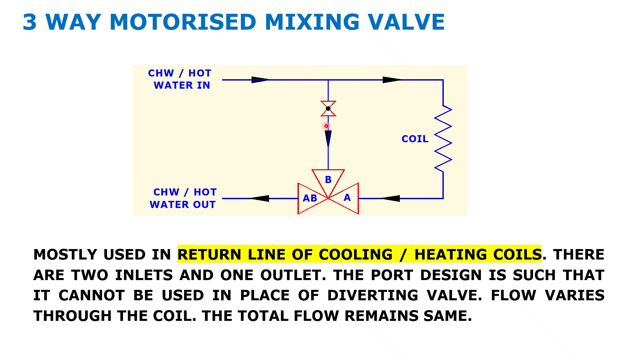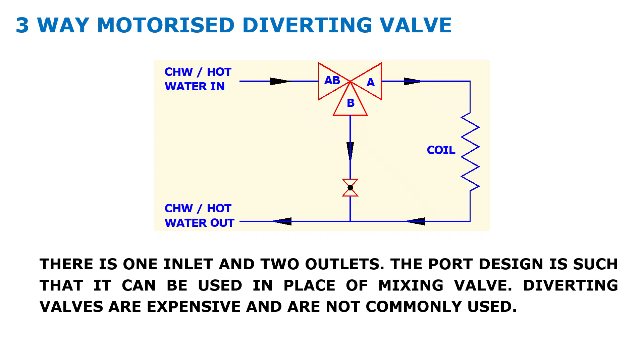A three-way motorized mixing valve is placed on the return side of a coil. When heating or cooling is not required, water is mixed back into the return; when it is required, water flows directly through the coil. A diverting valve is placed at the inlet of the coil, diverting water directly to the chilled or hot water return header when temperature is not required, and directing water through the coil when demand exists.